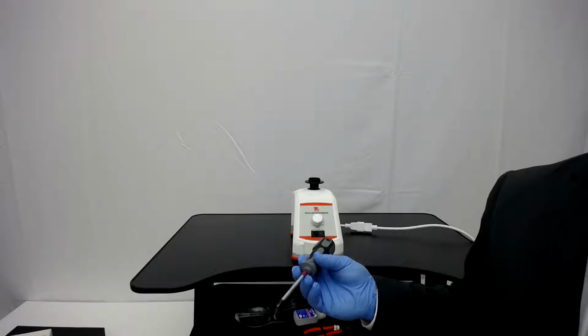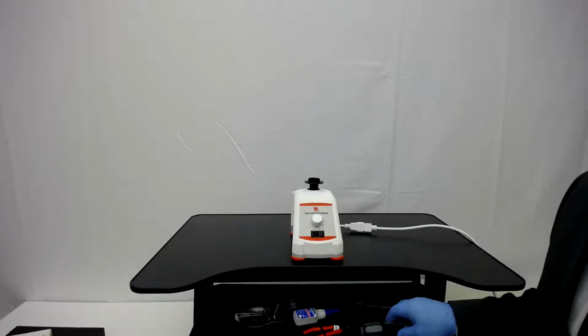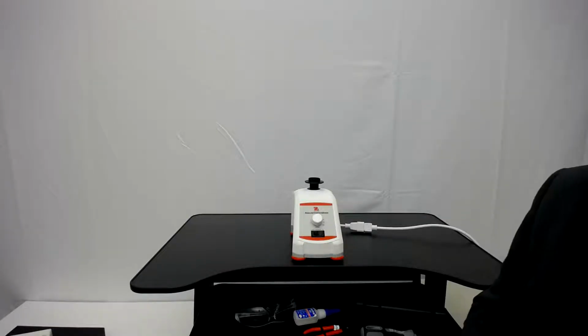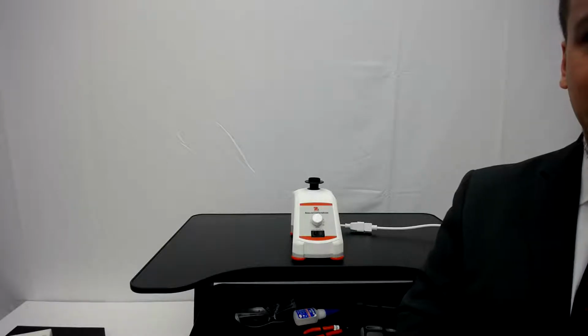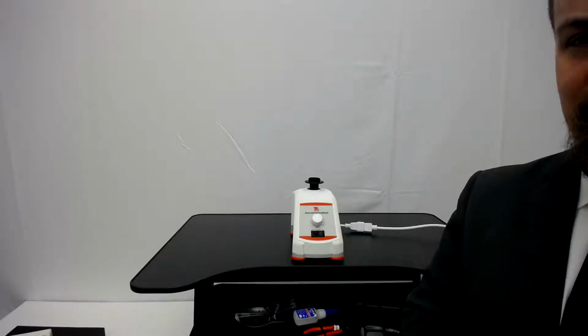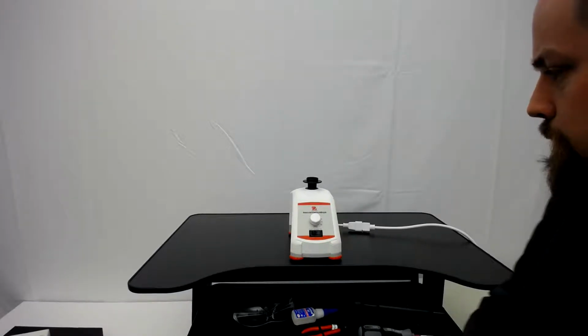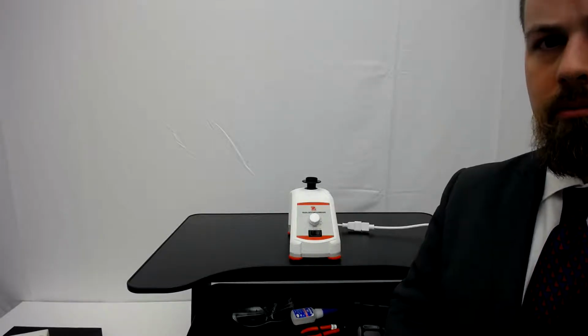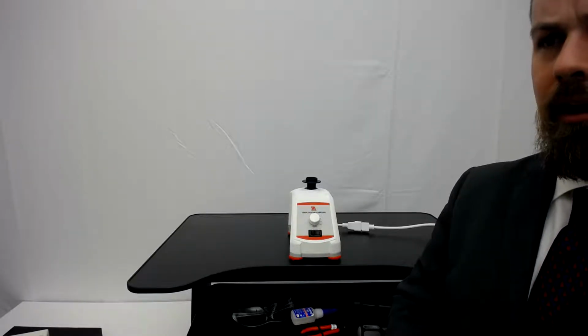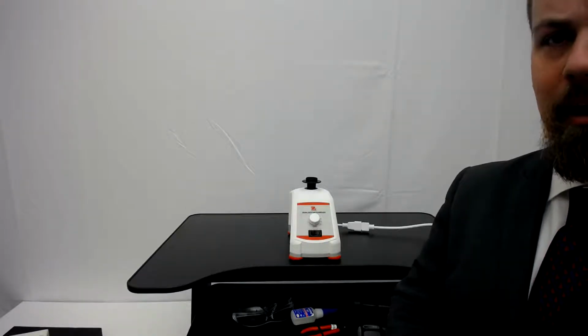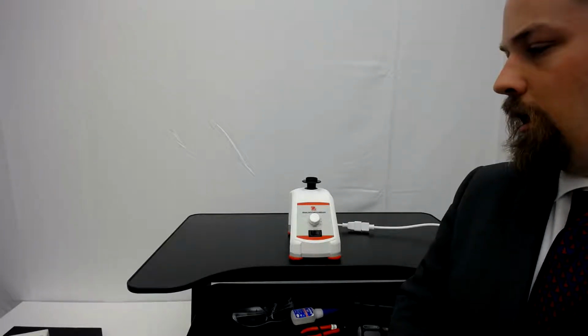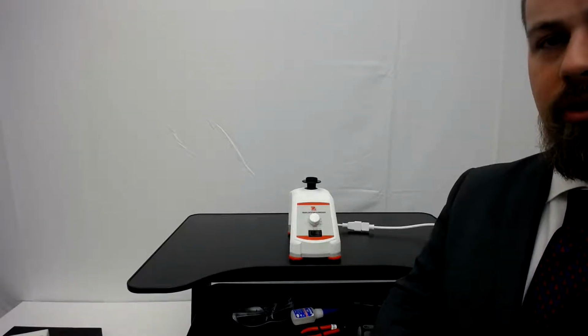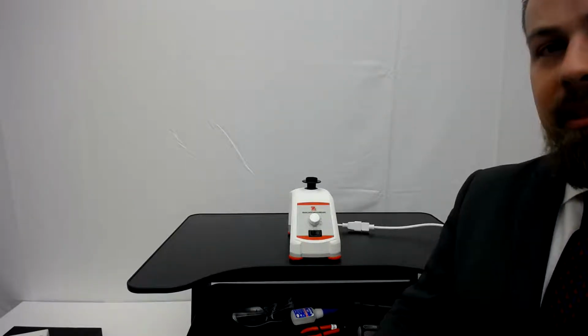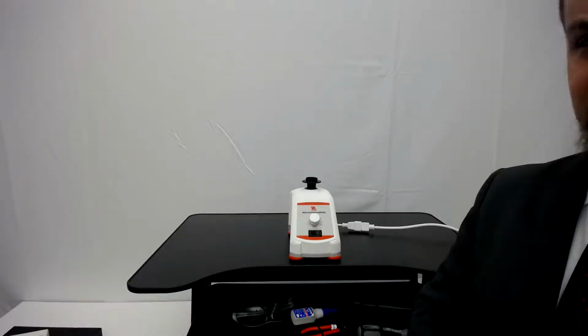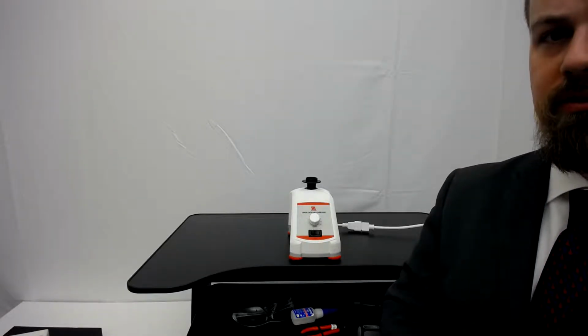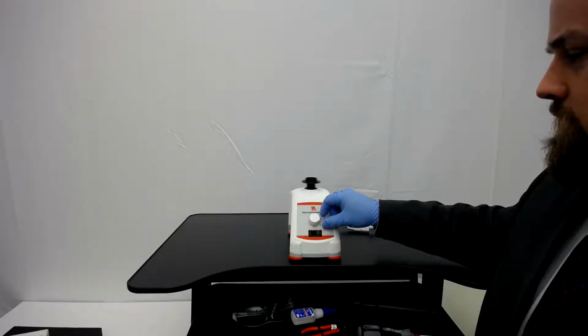As I go through this, I'm using hand tools, but refer to the specific torques that are in your manual. One thing I didn't say on the hot plate stirrer that's a little bit important is for both these units, before you go into the calibration, there is a burn-in time, a time where you run the unit before starting the calibration. That was all done before this presentation. So again, refer to your service manuals for the time that you have the unit running.